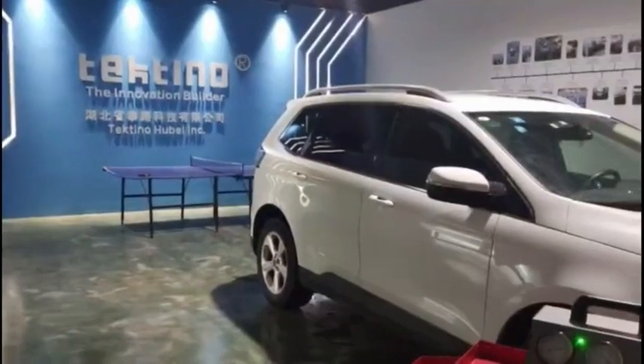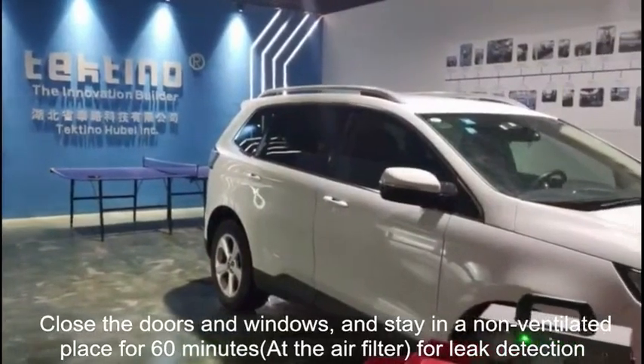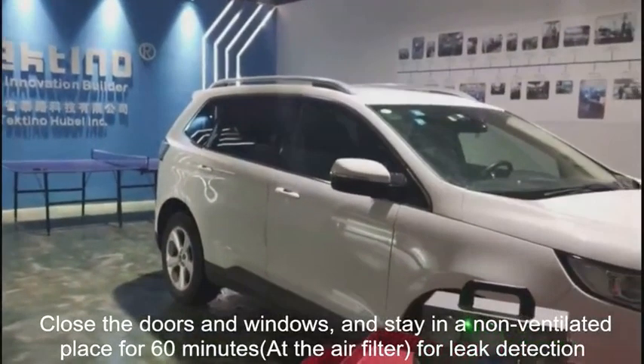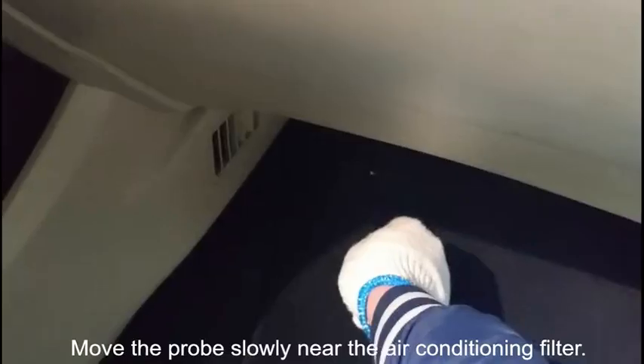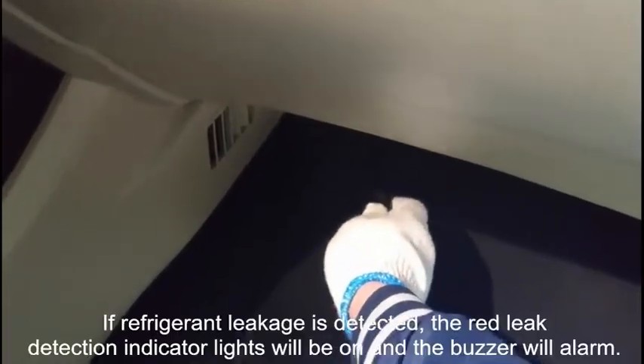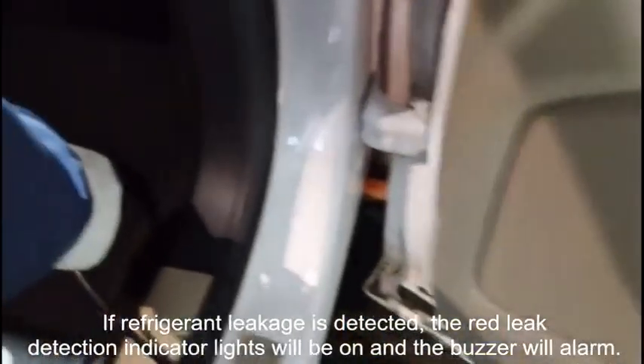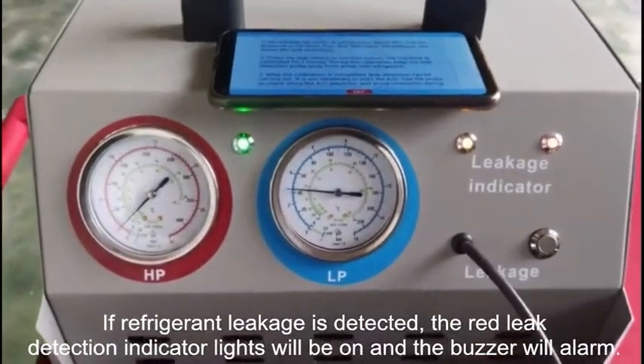Hidden parts leak test. Leak detection near the air conditioning filter port. Close the doors and windows, and stay in the non-ventilated place for 60 minutes, at the air filter, for leak detection. Move the probe slowly near the air conditioning filter. If refrigerant leakage is detected, the red leak detection indicator light will be on and the buzzer will alarm.